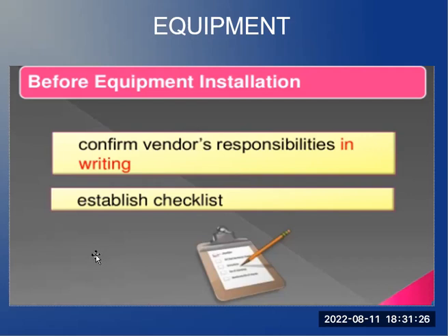then compatible reagents for that particular equipment, and your basic troubleshooting steps, which will be included in your checklist. And what else? The number of the engineers is important. It's either the biomedical engineer or the mechanical engineer, and the software engineer or the application specialist engineer, or application specialist.